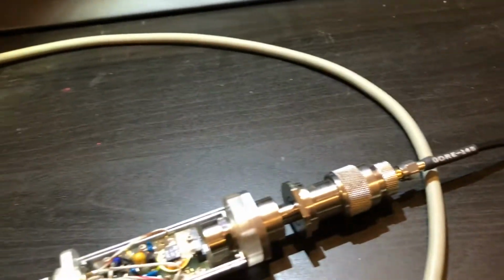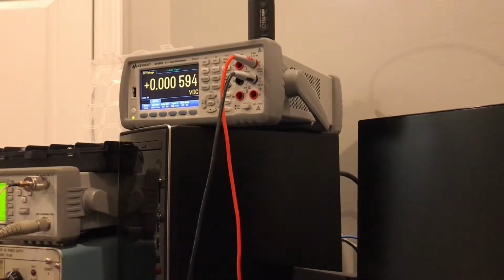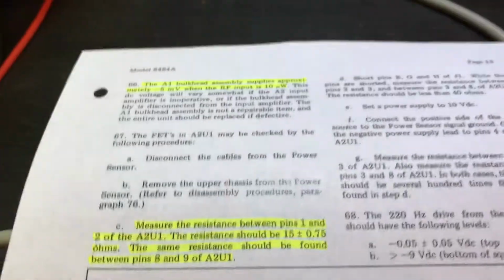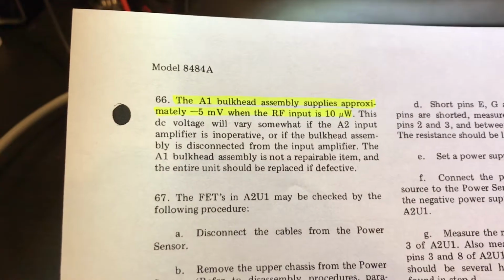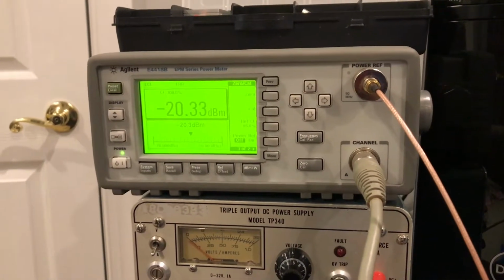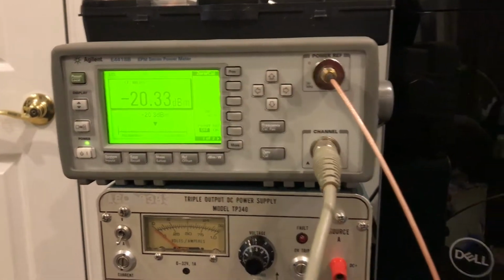So what we'll do is look at the signal up here on the multimeter. All right, so we're going to take that reading now, and on the schematic we're going to look at pin 1 and pin 9 of the A1 bulkhead assembly. So we'll take a reading on pin 1 and pin 9, and if you look at the multimeter, we're looking at minus 4.9 millivolts DC, which is according to the manual where it should be, approximately minus 5 millivolts when the RF input is 10 microwatts. So we know that the bulkhead assembly is putting out the right voltage, and based on the fact that we're reading a correct voltage on the power meter, it's relatively safe to assume that the rest of the circuit is working.